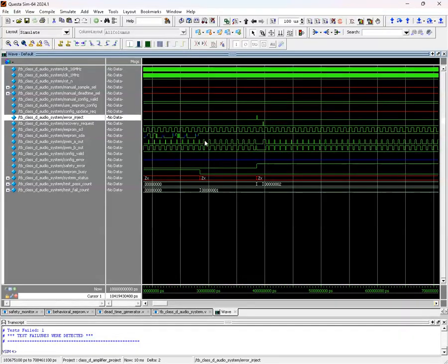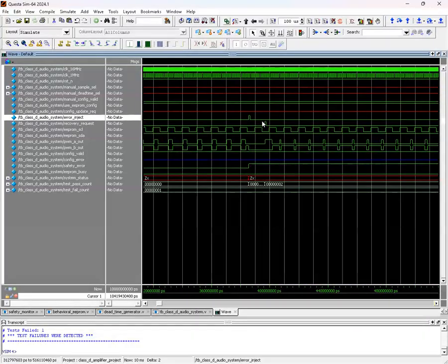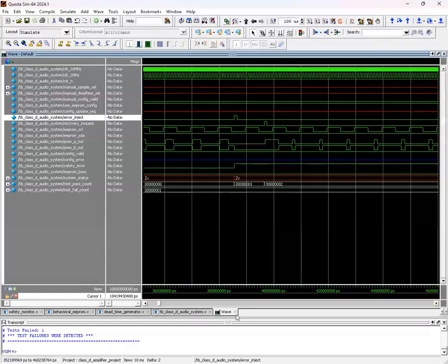You notice the PWM is running all over here, right? And this is what I'd like to show. When you're looking at the PWM running here, running fine, and I inject an error in the test bench, so I send an error here, both PWMs drop to low. The cycle over here dropped to low, and this here dropped to low as well. So both have gone to low.